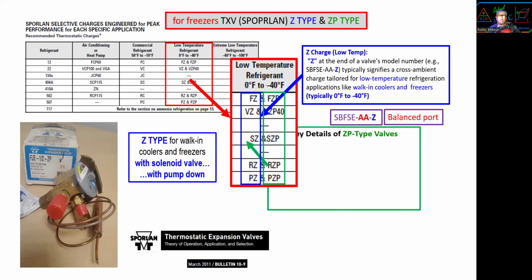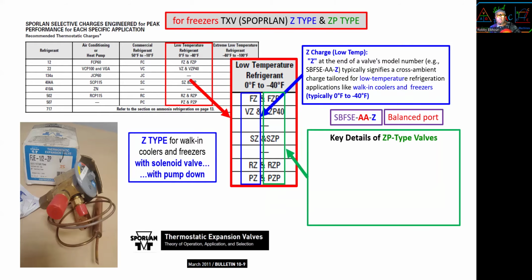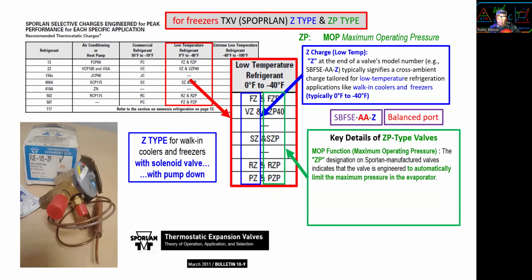This is important because we have the ZP type. ZP is a MOP, maximum operating pressure, all right? Maximum operating pressure is designated with the Sporlan designation. It means it will automatically limit the maximum pressure in the evaporator. It prevents the compressor motor from overheating by limiting pressure after system pull down.